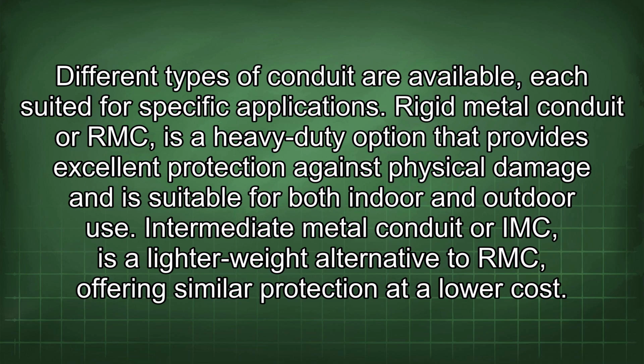Different types of conduit are available, each suited for specific applications. Rigid metal conduit, or RMC, is a heavy-duty option that provides excellent protection against physical damage and is suitable for both indoor and outdoor use. Intermediate metal conduit, or IMC, is a lighter weight alternative to RMC, offering similar protection at a lower cost.